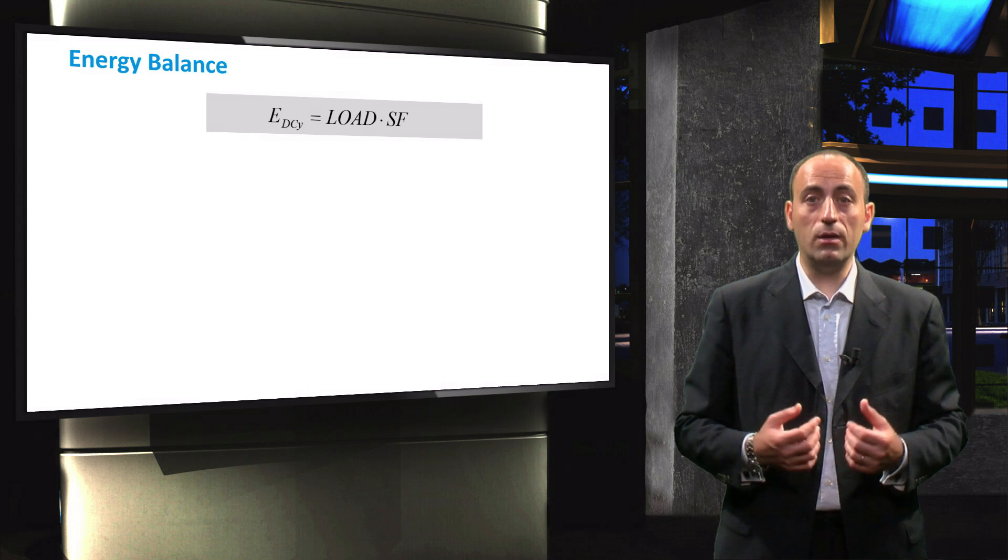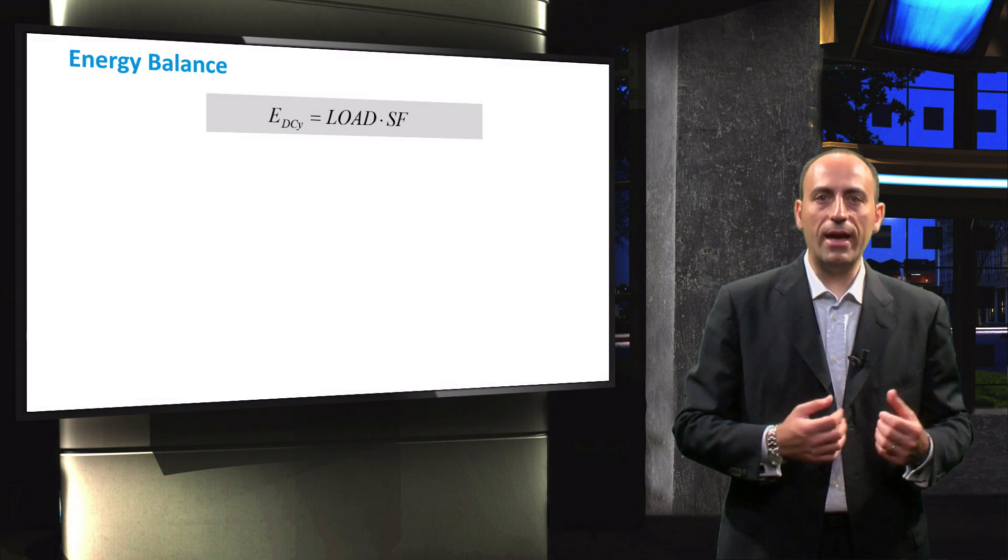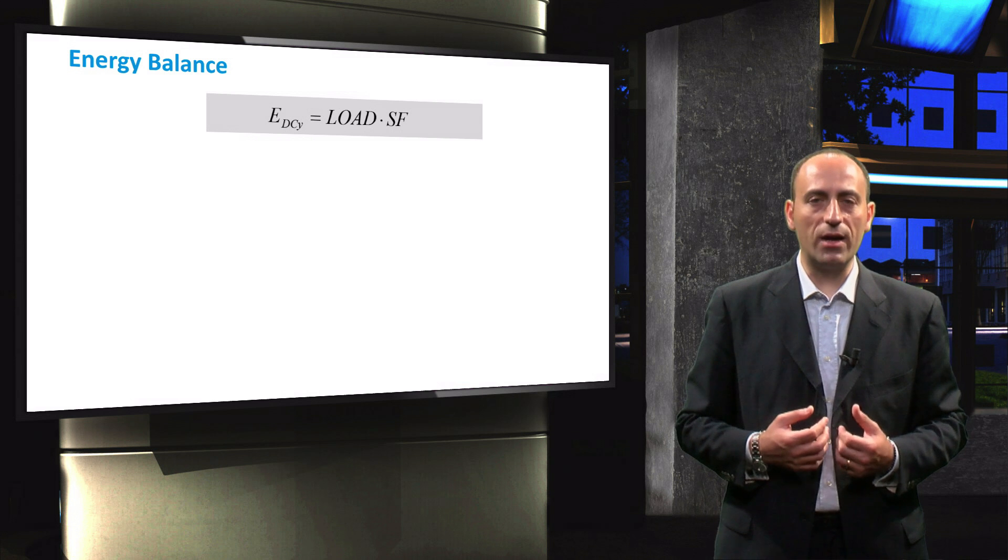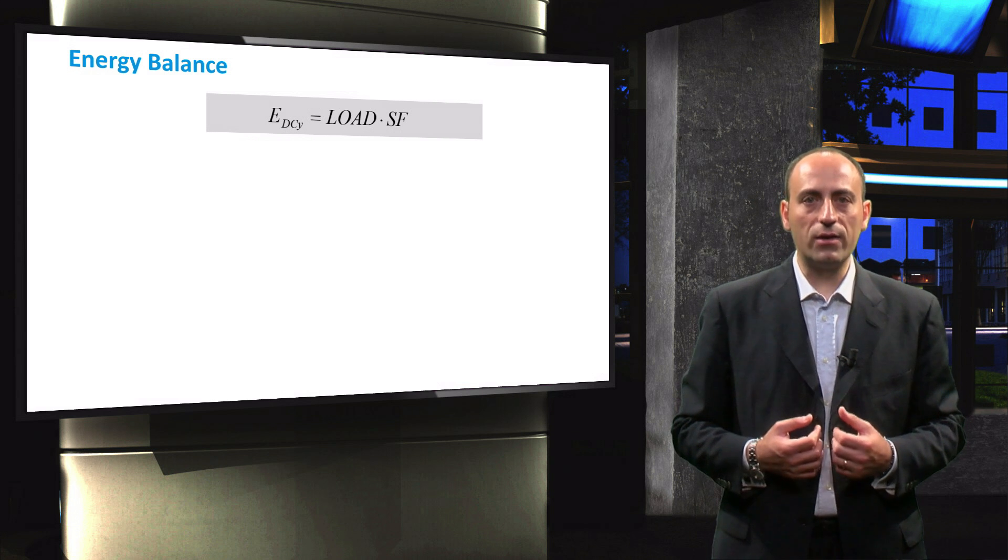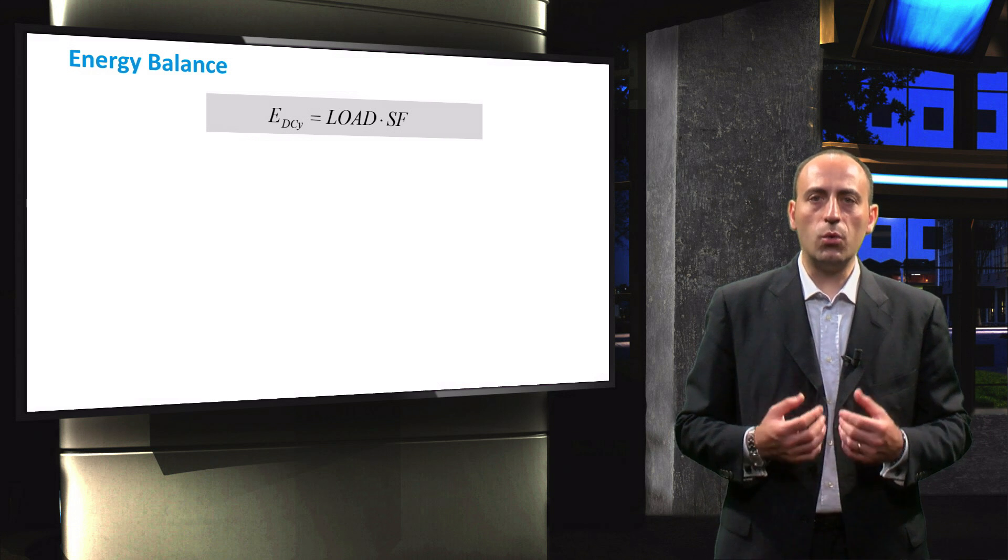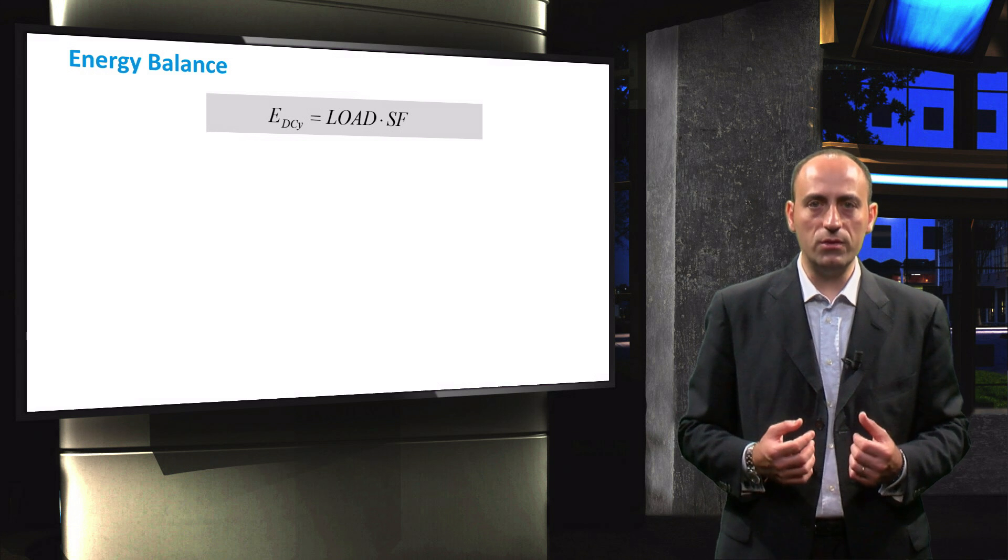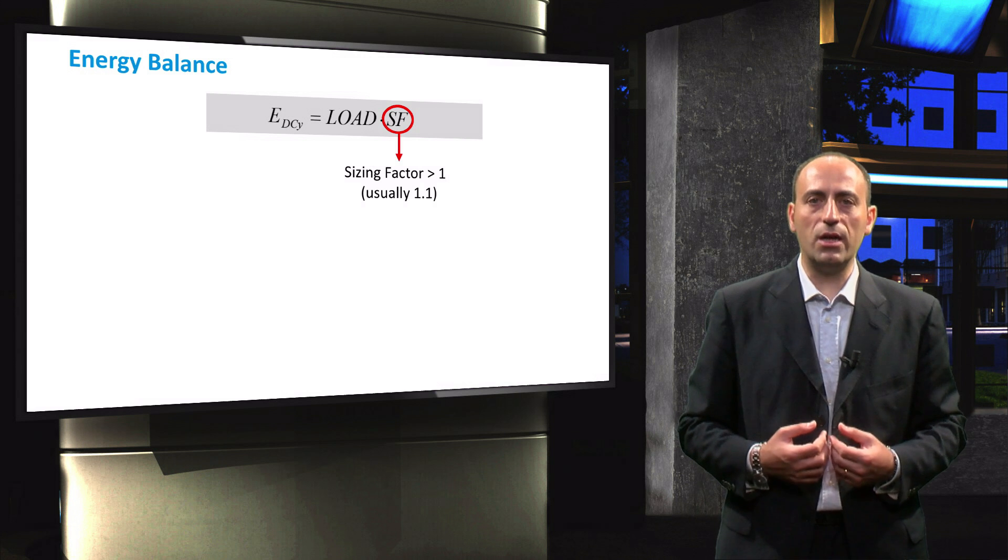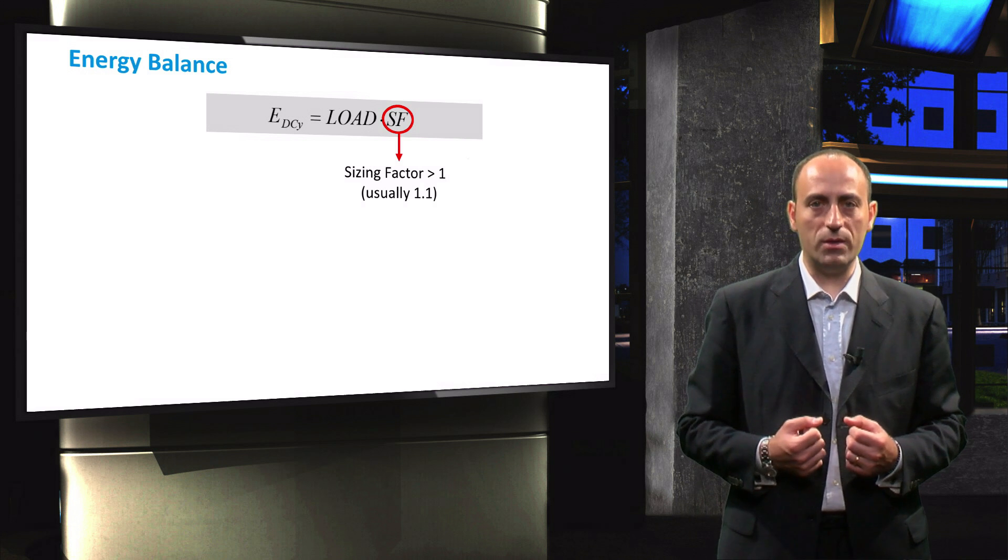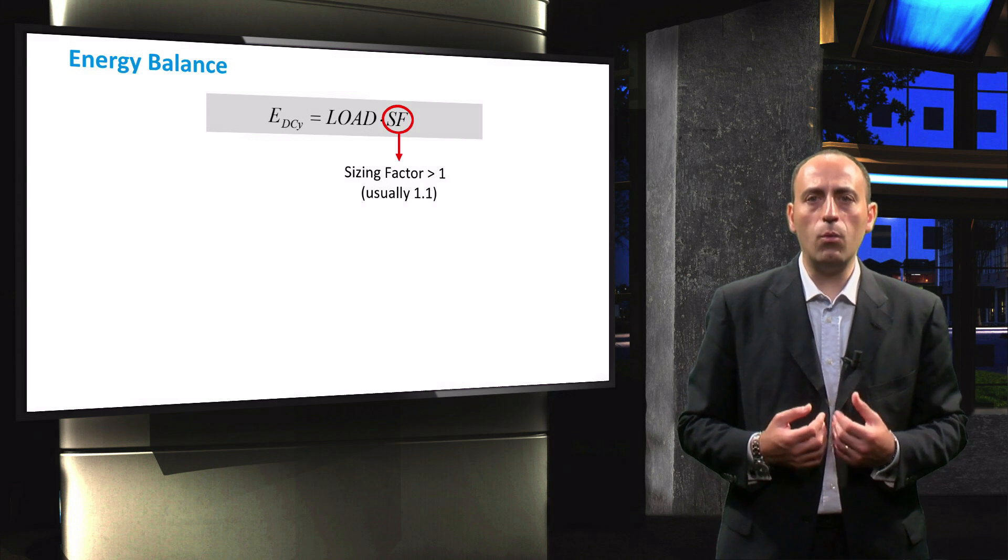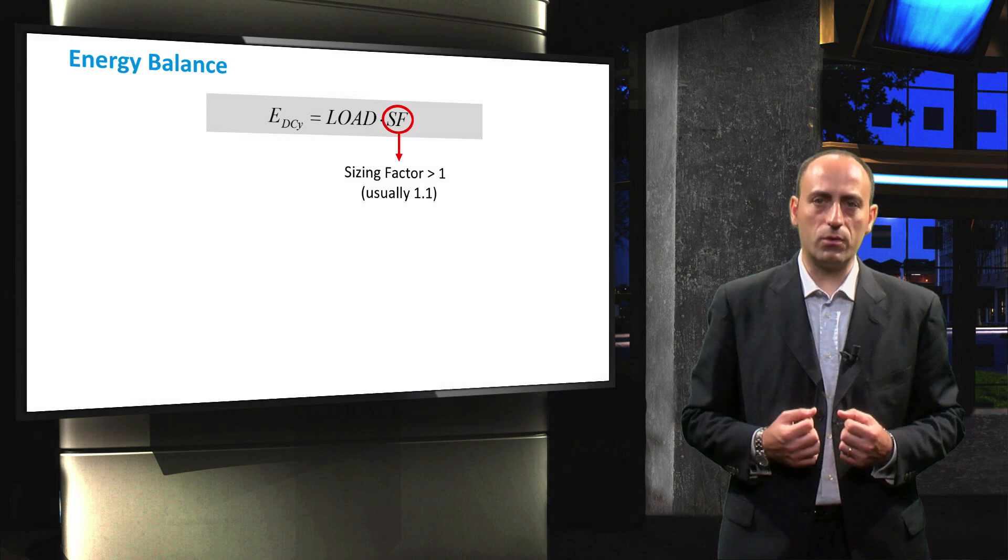Now we know the annual load demand and the annual energy generation. To complete the energy balance, we introduce a sizing factor, SF. The system sizing factor is a flexible value that provides a certain degree of freedom to adjust the PV system size during the design phase. It is inserted to allow for additional losses such as the accumulation of dirt on the modules, or to increase the system performance. The value of the sizing factor should be greater than 1, and the value of 1.1 is usually assumed as a first approximation.